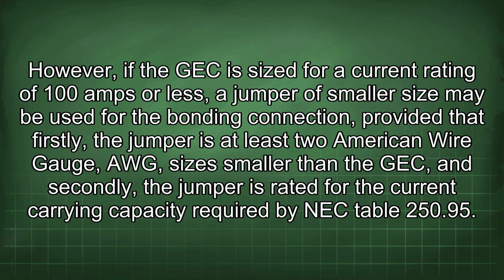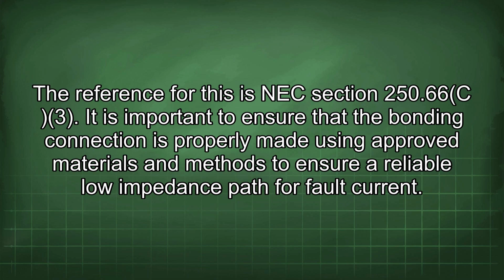However, if the GEC is sized for a current rating of 100 amps or less, a jumper of smaller size may be used for the bonding connection, provided that firstly, the jumper is at least 2 American wire gauge, AWG, sizes smaller than the GEC, and secondly, the jumper is rated for the current carrying capacity required by NEC table 250.95. The reference for this is NEC section 250.66(c)(3). It is important to ensure that the bonding connection is properly made using approved materials and methods to ensure a reliable low impedance path for fault current.